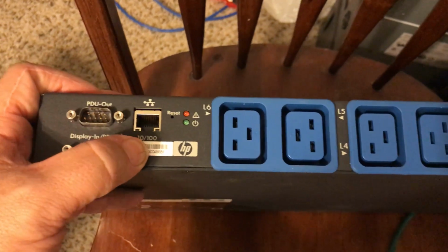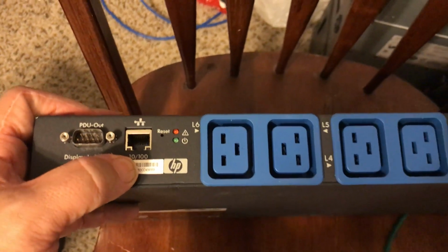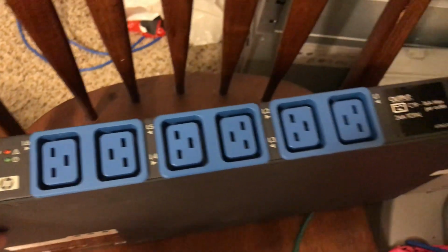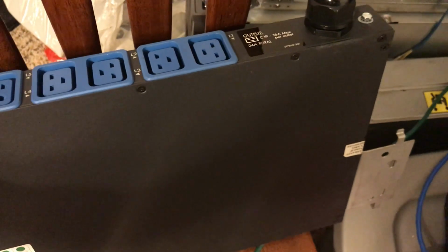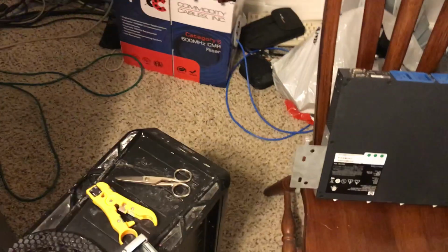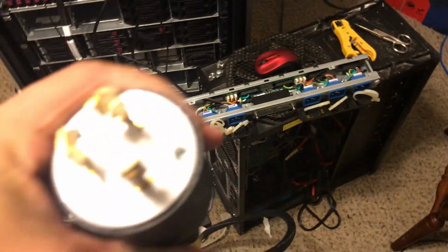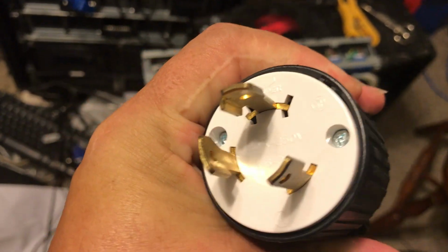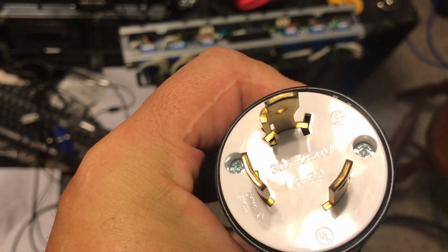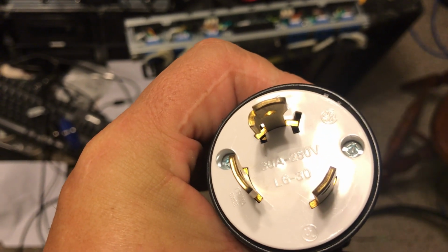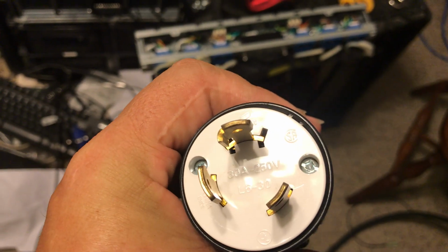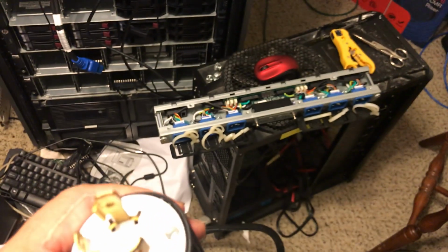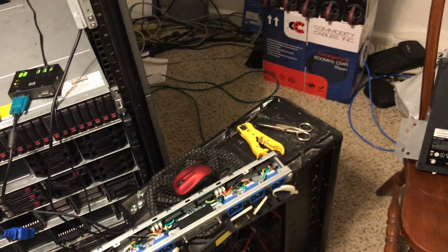You also have a dedicated Ethernet port - yeah, that's right, it's a PDU with an Ethernet port. This way you can monitor your giant load segment, because on the end of this cable it actually says - yeah, you can see it right there - this is a 250 volt, 30 amp cable. When you draw that kind of power, and there are 2 of them, one per side, on separate breakers, you have to monitor how much current you're actually using.